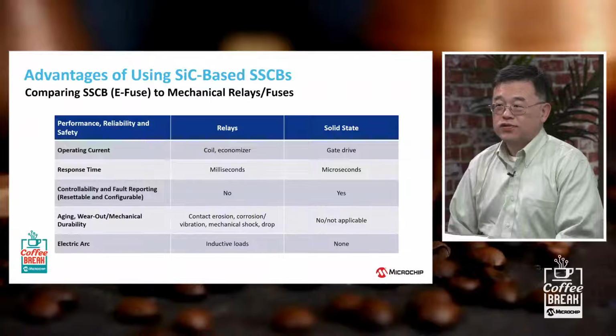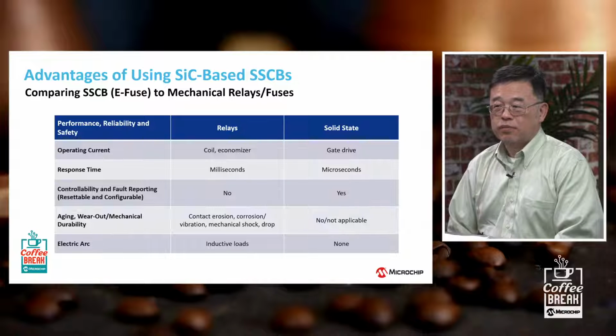Back from our season 10, episode 3, we discussed primarily five main areas. One is the operating capability of the circuit breaker. It uses silicon carbide MOSFET devices and silicon carbide gate drivers. As a result, it's very compact, and does not require all these bulky economizers and coils to both pre-charge as well as switch and de-energize the circuit breaker. So it's a very compact system and a very high-performance silicon carbide-based switch.